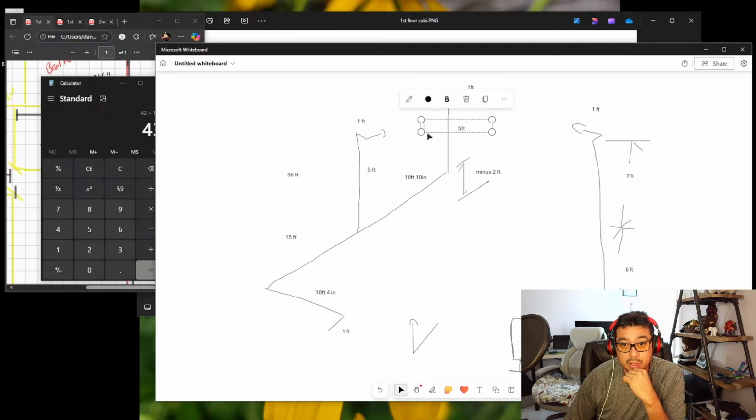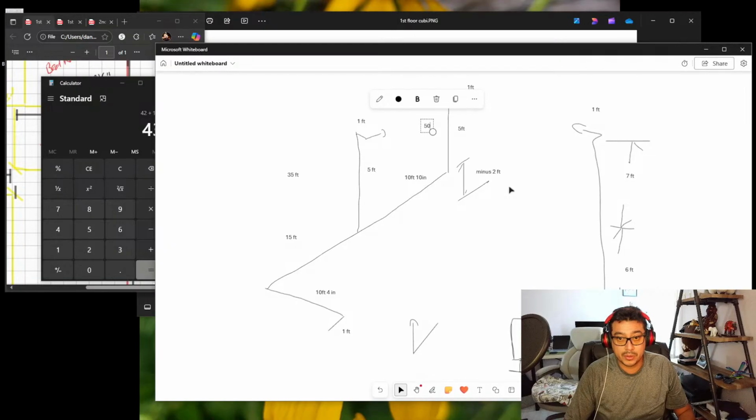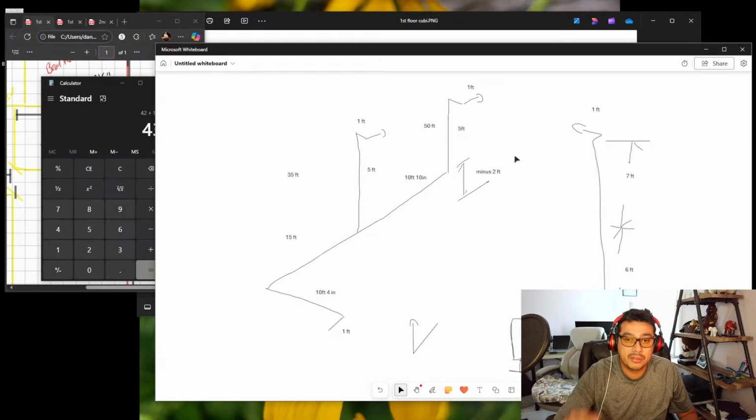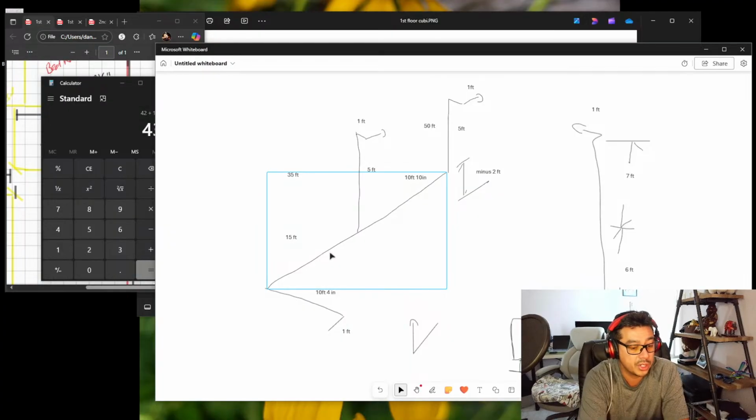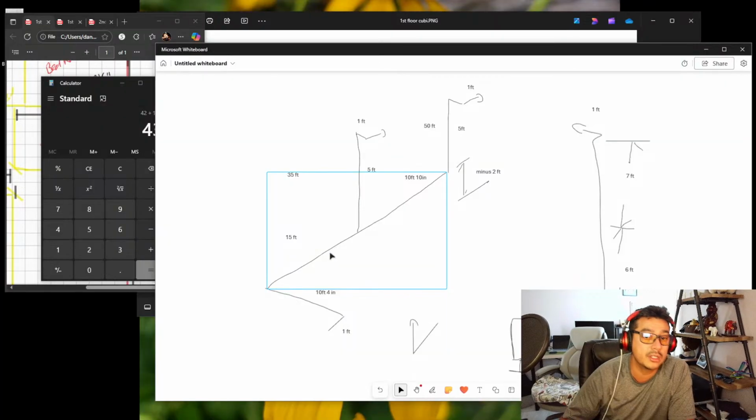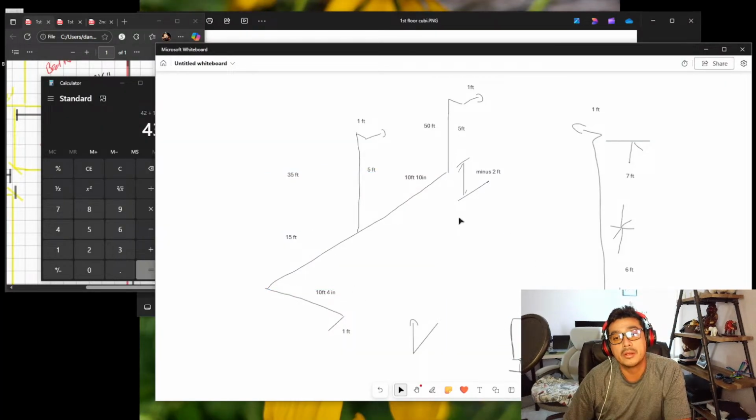There's no way I'm ordering 35, 35, and then making a connection right in the middle. That's ugly. We want to stay solid from point A to point B. Not only do we need to take these measurements for these guys, but that's also how we charge a system. I think it's 0.6 ounces for every foot of line set. Good. So that's a 50 footer.